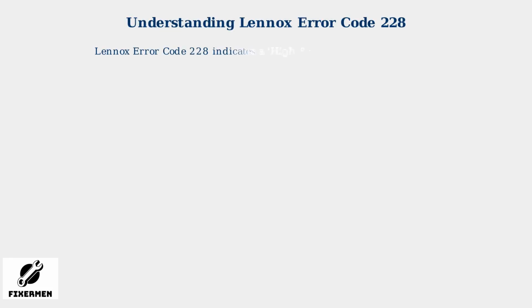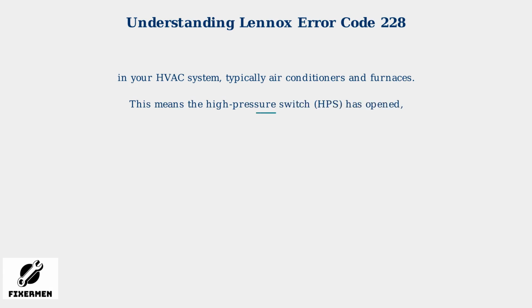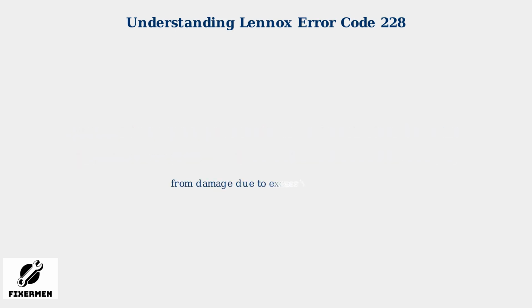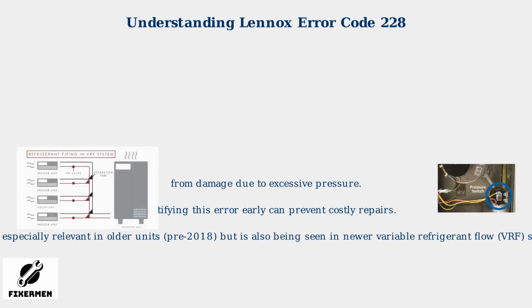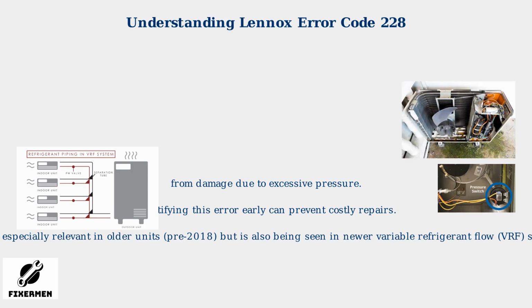Lennox Error Code 228 indicates a high-pressure switch open fault in your HVAC system, typically air conditioners and furnaces. This means the high-pressure switch, or HPS, has opened, suggesting the refrigerant pressure is too high or the switch is malfunctioning. The high-pressure switch is a safety device designed to protect the compressor from damage due to excessive pressure. Identifying this error early can prevent costly repairs. This is especially relevant in older units before 2018, but is also being seen in newer variable refrigerant flow systems.